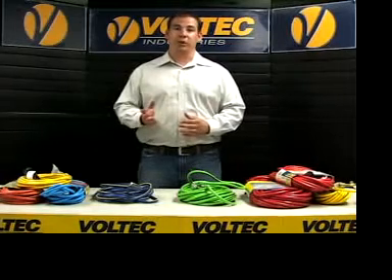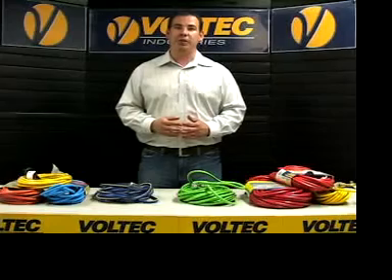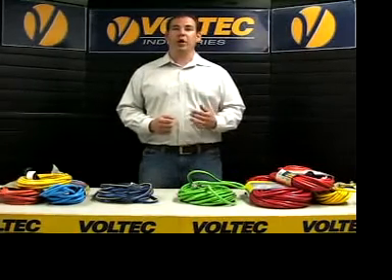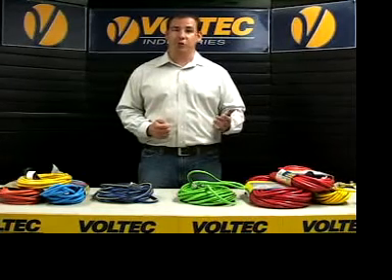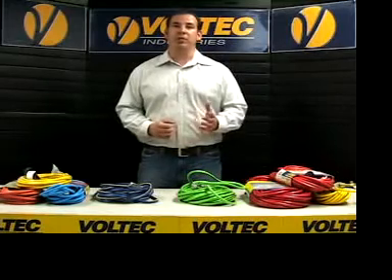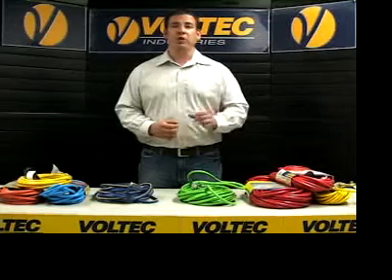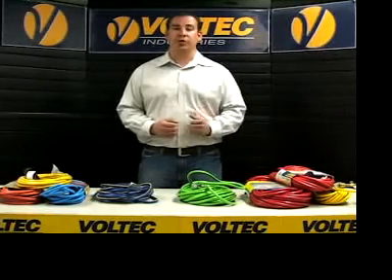As with other flexible cords, the NEC also prohibits extension cords from being attached to a building surface, concealed inside of a wall, floor, or ceiling, or above suspended ceilings, or run through holes or other openings in structures. Cords run across the floor should be covered with a suitable device to protect them from physical damage. Extension cords bearing the UL mark will give your safety inspector confidence that power is being distributed safely.